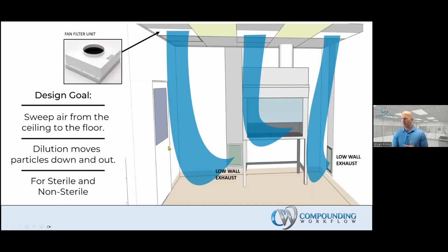Let's talk briefly about USP 797 and 800. There's an intertwinedness, but USP 797 says HEPA filtered air must be introduced at the ceiling, and then there's a preference for low wall returns—called returns in 797, exhausts in 800, depending on whether they're recirculating or not. They're placed low to the floor, about 6 to 10 inches above the finished floor.